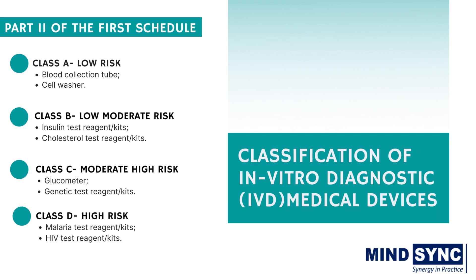We will then go on to the in vitro diagnostic medical devices classification. IVD are categorized separately from other medical devices. The central licensing authority shall classify IVD devices on the basis of intended use and parameters specified in Part Two of the First Schedule of Medical Devices Rules, in the following classes. Class A denotes low risk — for example, blood collection tube, cell washer. Class B is low to moderate risk — for example, insulin test kits, cholesterol test kits. Class C denotes moderate to high risk, such as glucometer and genetic test kits. And Class D is high risk — for example, malaria test kits and HIV test kits.